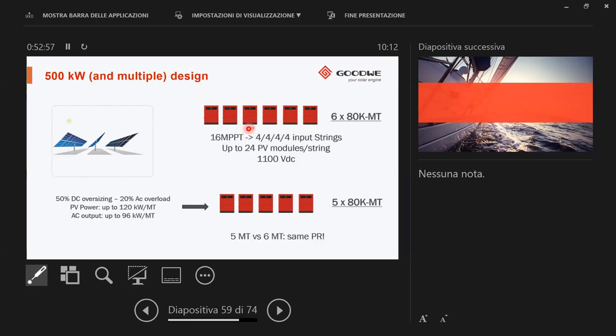But together with this, you should consider the capability of having 16 MPPT, for each MT inverter has 4 MPPT. So you can multiply this in order to also manage a more complex configuration of your design. For each inverter, you have the capability of using 4 strings for each MPPT, meaning 16 strings connected. And on each string, you can install up to 24 PV modules with an entrance voltage of 1100 volt DC. So according to our experience, this is the most logical configuration for the 500 kilowatt solution, but also, as I said, for multiple realization.